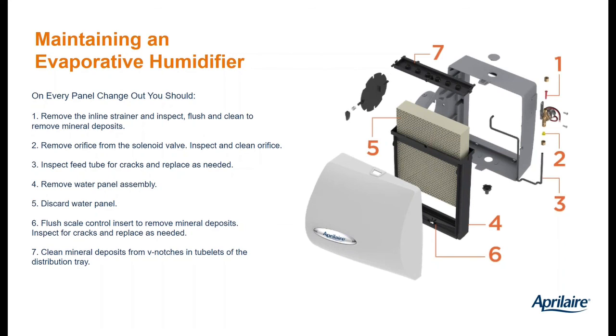3 gallons per hour or 6 gallons per hour. Easy to ream that out and get way too much water going through it. I've seen guys try and clean out that strainer that keeps debris from entering the solenoid valve, end up tearing holes in it. They're trying to do a good thing and they wind up just letting debris from the water heater get into the solenoid valve and plug it up.